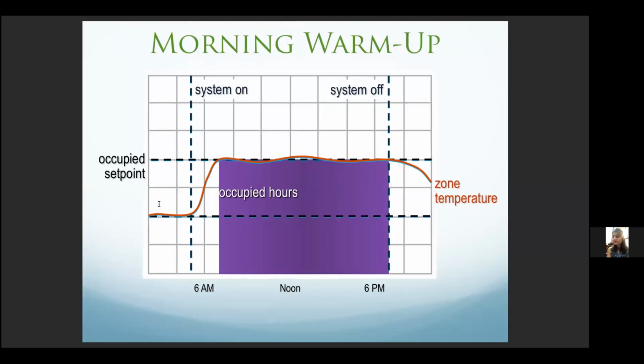So morning warm-up is an optimization strategy that is used to heat up the space in the morning, for example. If there's an office building that gets occupied at 8 a.m., the system level controller says, okay, it's going to get occupied at 8, so at 6 o'clock I'm going to turn on the system. I'm just going to close all the outdoor air dampers, and I'm going to recirculate the air and make it hot and make sure that it is good to go before the building opens up at 8. Now, what it notices is that, hey, look, it only took me 1 hour instead of 2 hours yesterday to heat up the building. So instead of 6 a.m. tomorrow, I'm going to start at 7 a.m. And you save that extra hour of energy usage.